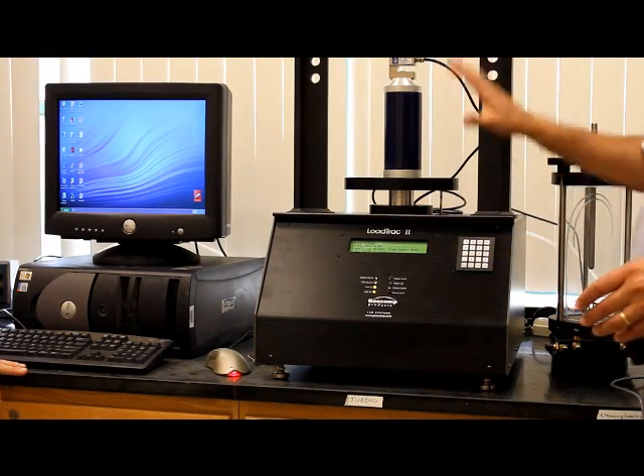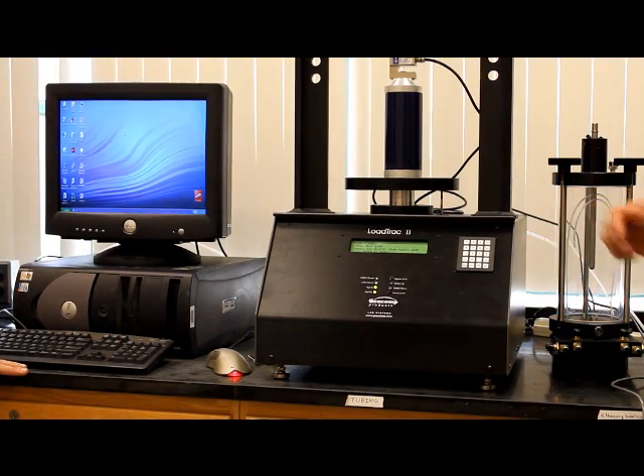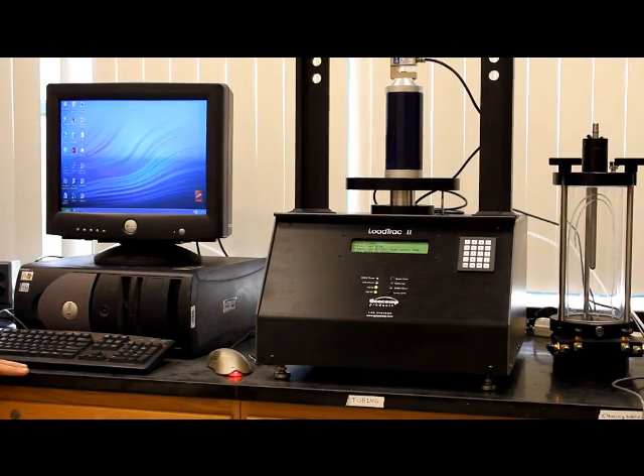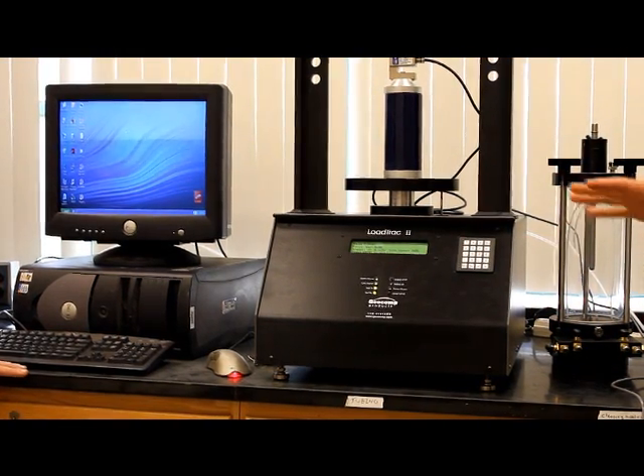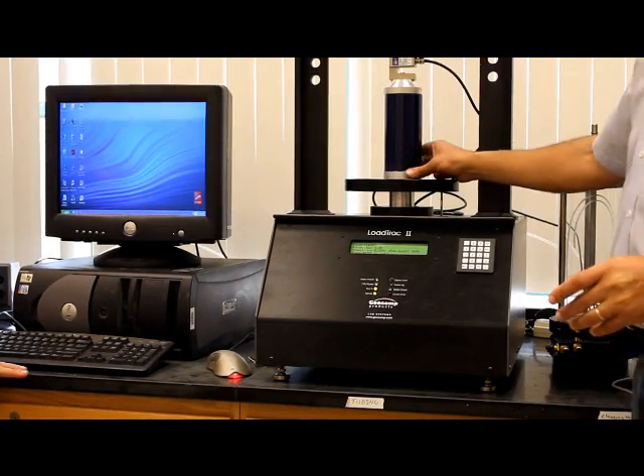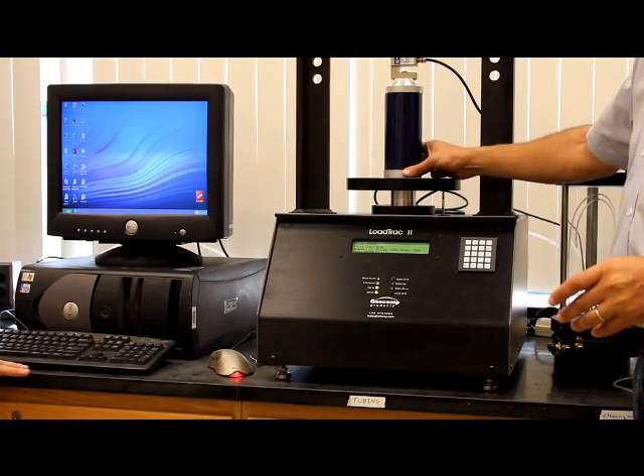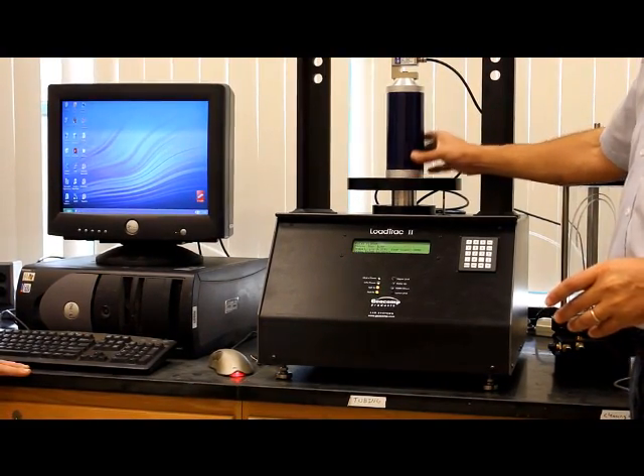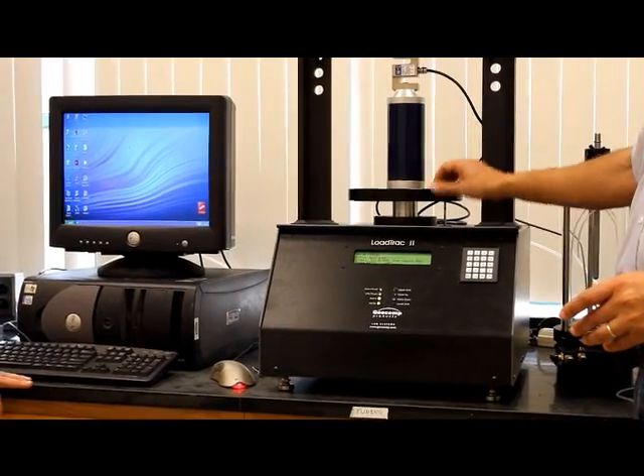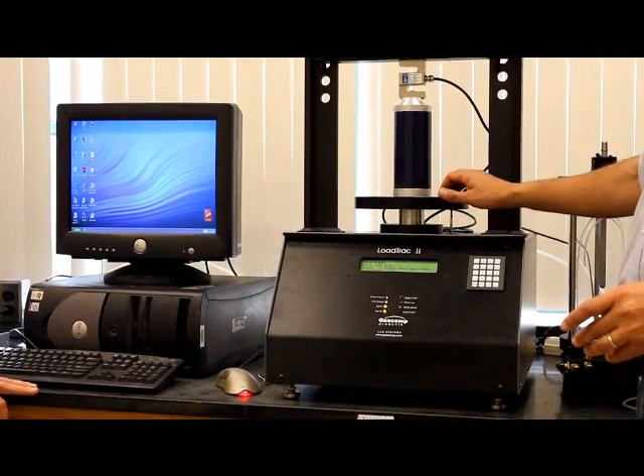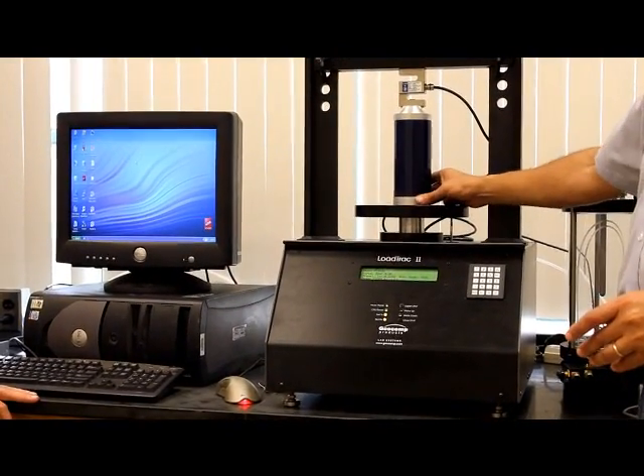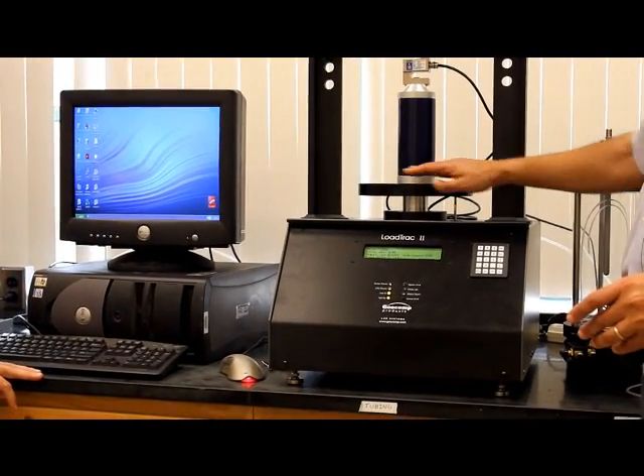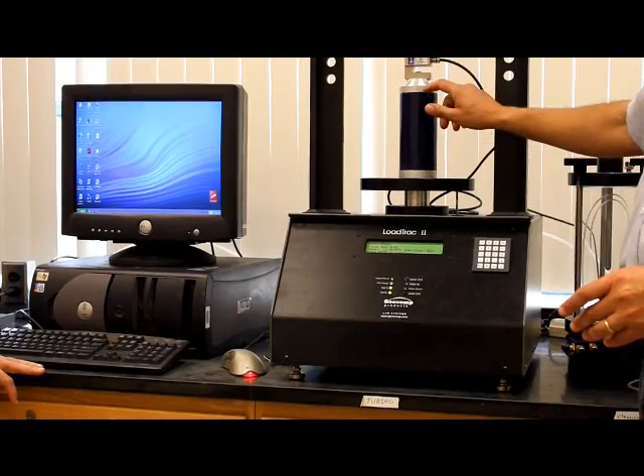Okay, we are going to run a unconfined compression test from scratch. Most important thing is to trim a good sample, take all the dimensions and the weight. We set the sample onto the platen.